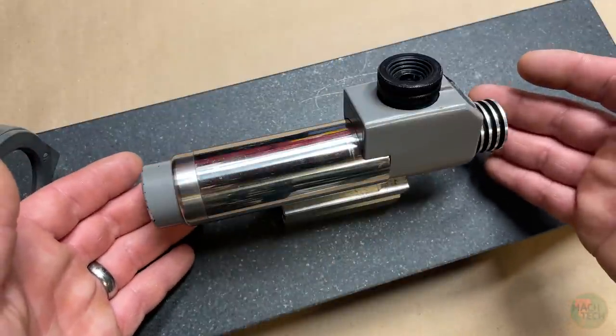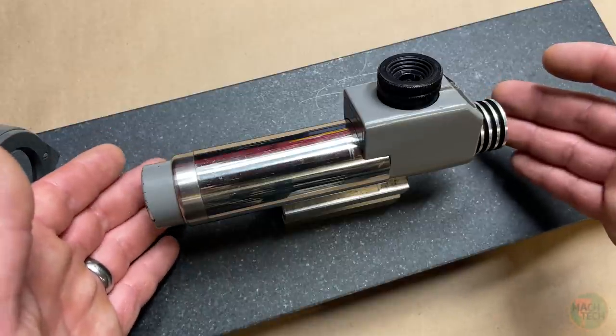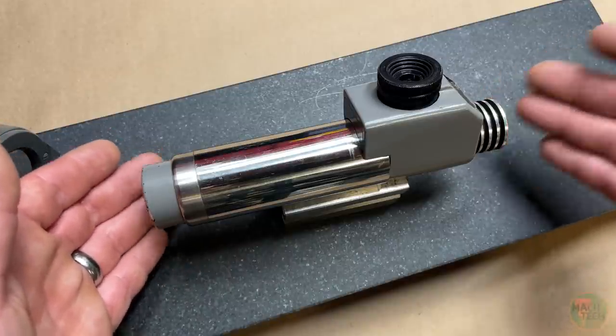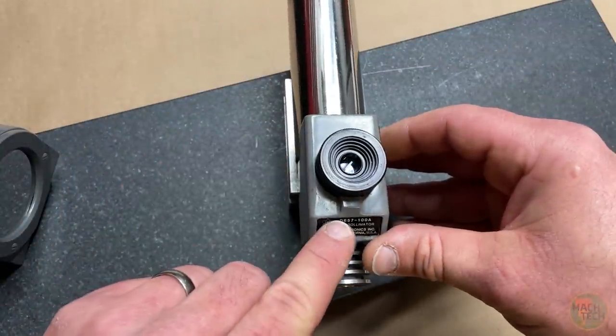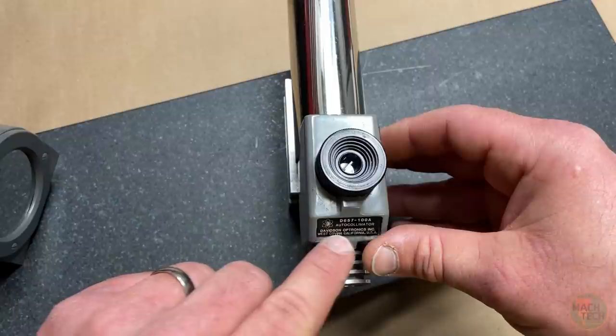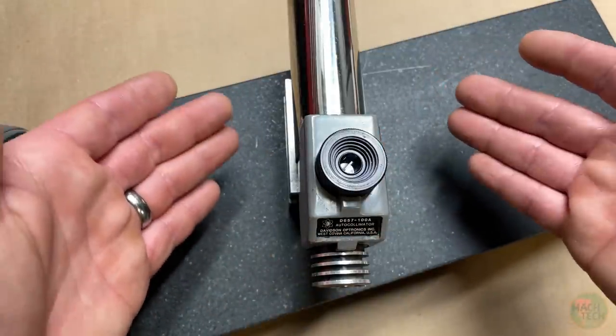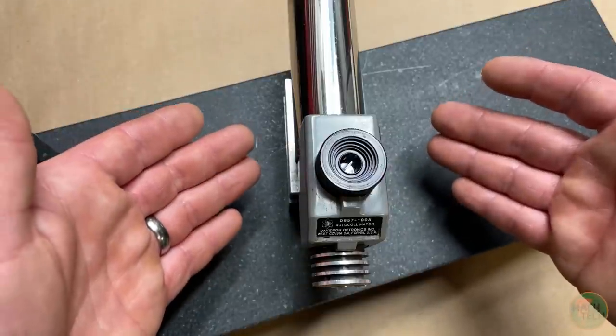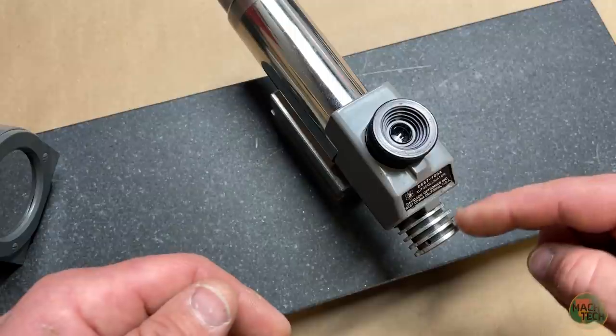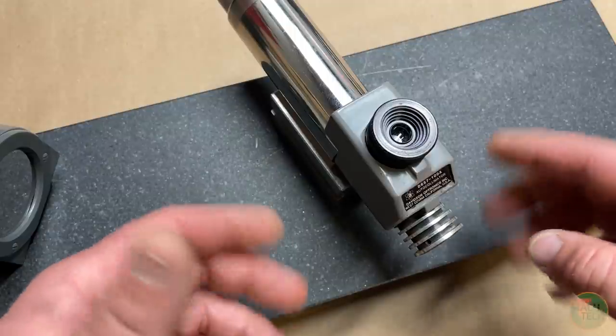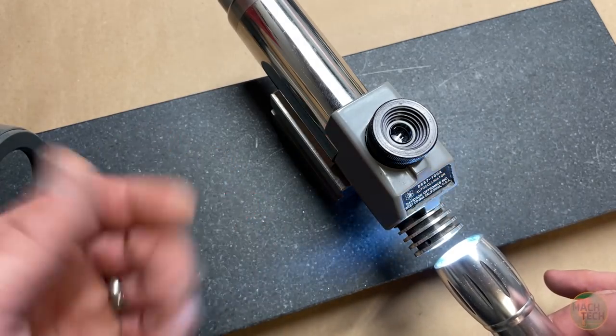This is an auto collimator. It's the simplest one that I own in terms of its design, so it's a good example to illustrate the key elements of auto collimators in general. This is a model D657, made by the Davidson Optronics Company. They've pretty much obsoleted everything in their product line, but back in the day, they made some really cool stuff. Now the way that it works is that you shine a light through this port right here, and actually this one is missing its light source, but they're pretty easy to make. You can even use a flashlight. It works just fine.